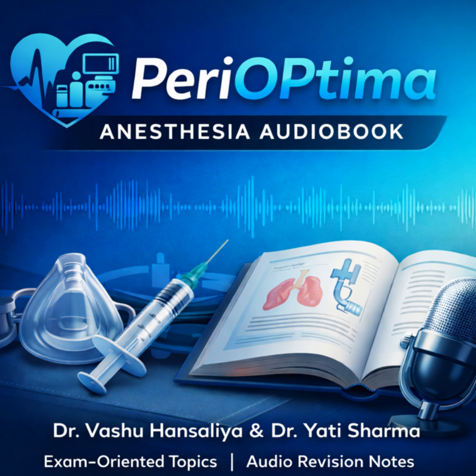Huge risks. Barotrauma. 75 liters per minute is like a fire hose. Yeah. If you press that button while the patient is connected to a ventilator during the inspiratory phase, when the lungs are already full and the valves are closed, you can blow out a lung. You can cause a tension pneumothorax. So the rule is? Never, ever press the flush button during inspiration.